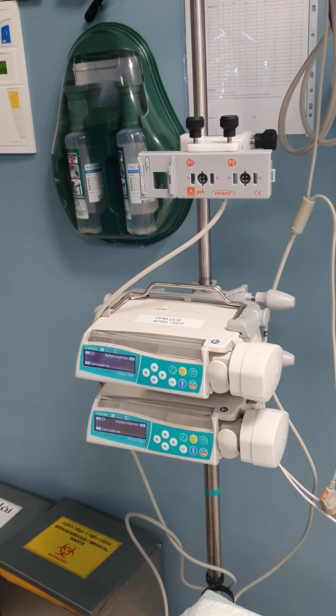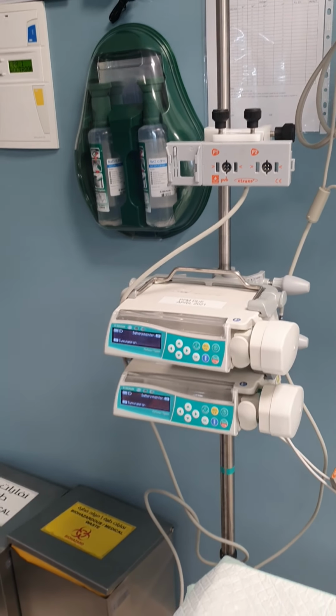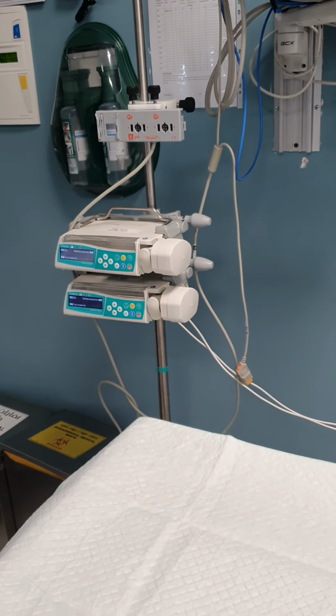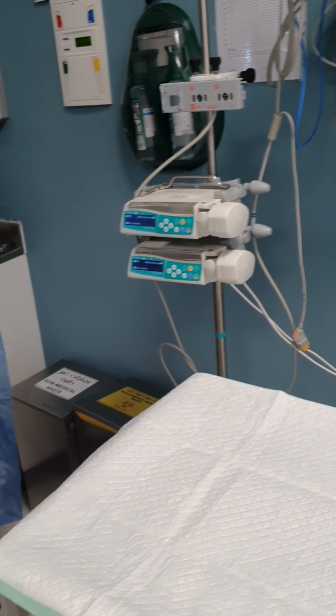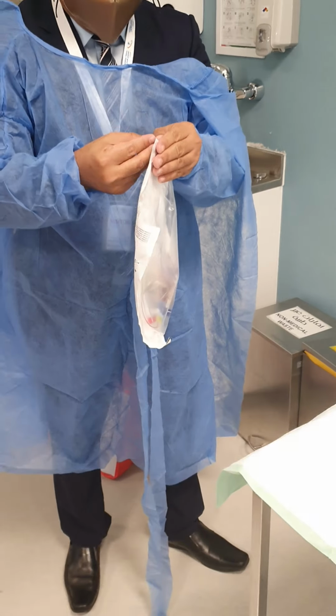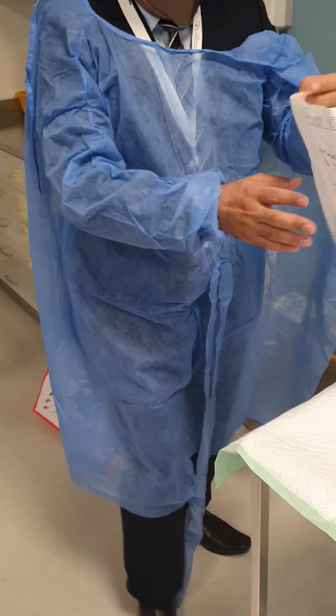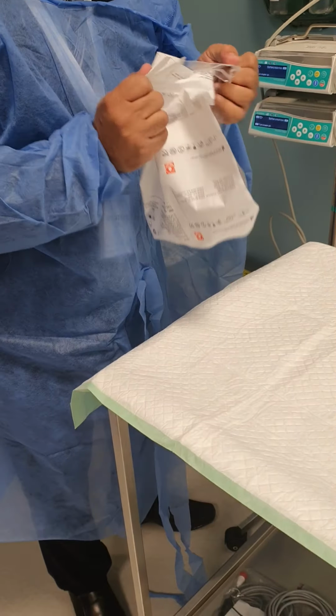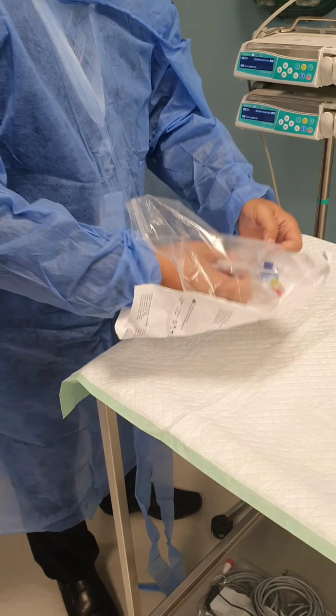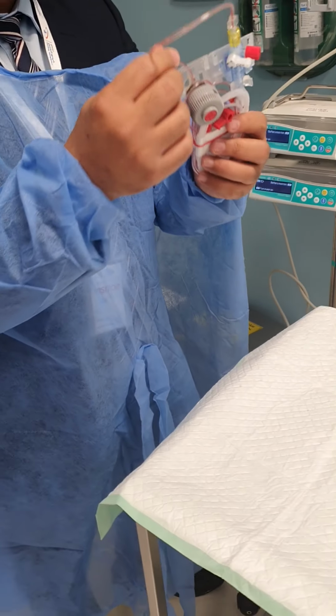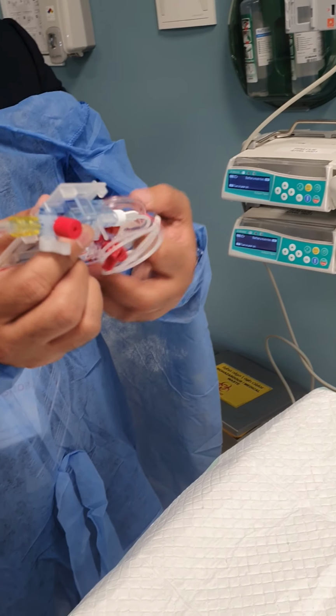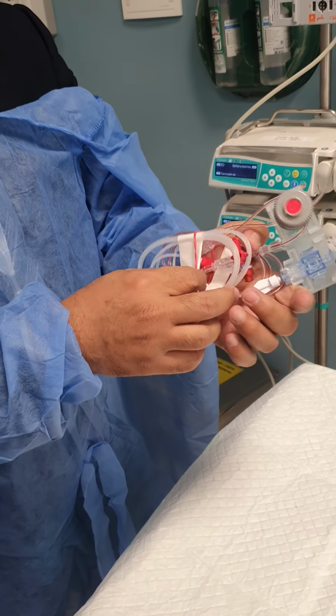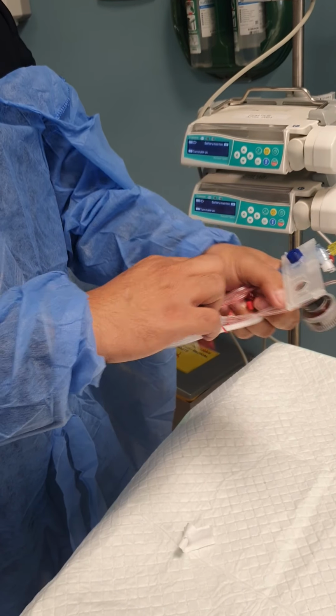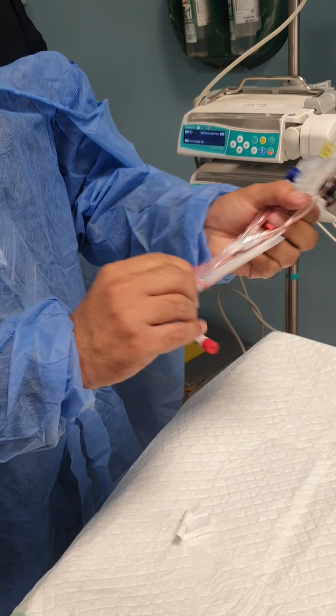How to prepare and use the Codan PVB transducer sets. So this one is actually for arterial line. Just to open it. This is specifically made for neonates. It has a smaller bore and shorter extension tubing. Primarily it can be used for the syringe pumps, because for adults it's with the bag, the pressure bag.